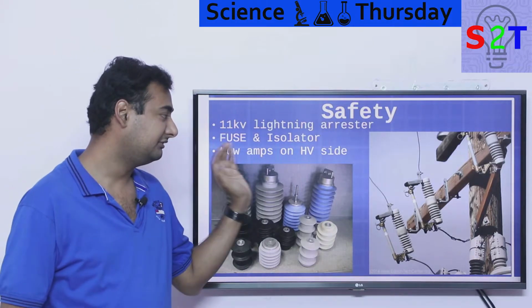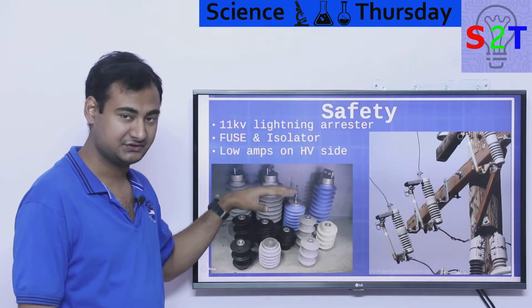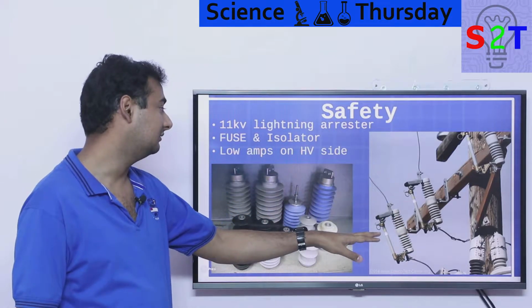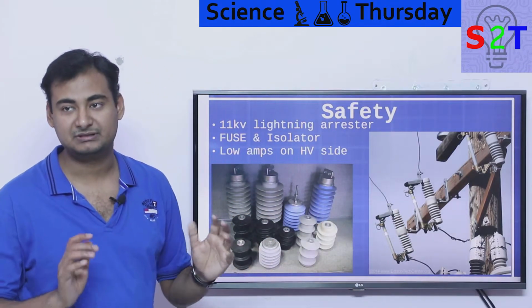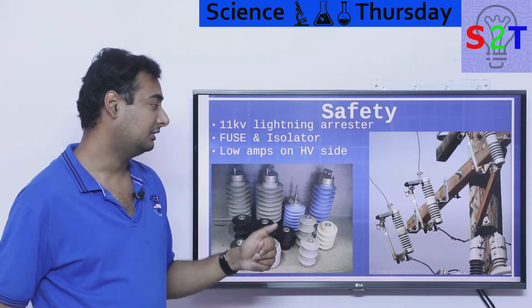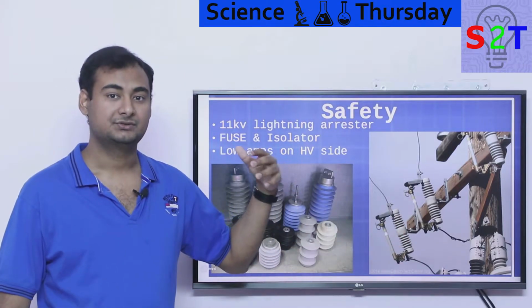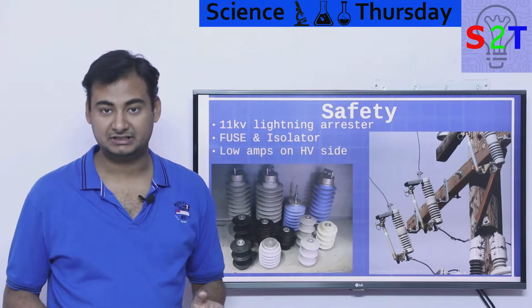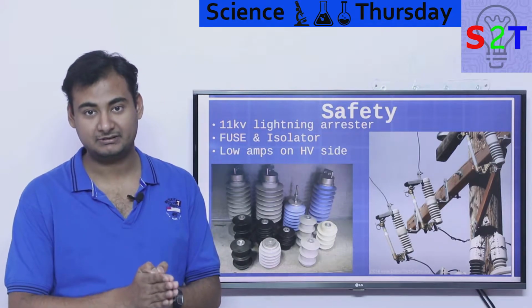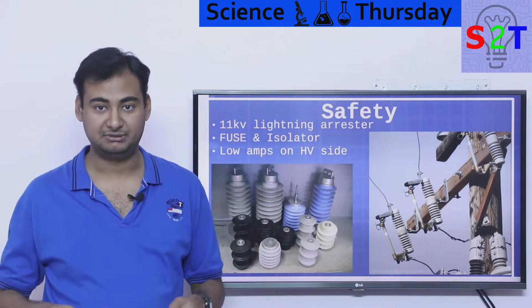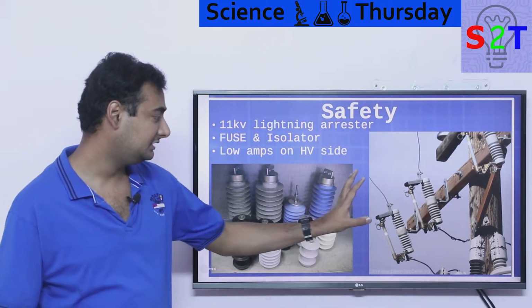On top of that, after this first line of defense, we come to the fuse and isolator. Isolator simply means you are pulling the plug. You have to understand this is a combo unit; in a substation these two would be completely separate, a fuse controlled by a circuit breaker and an isolator completely independent. Here we don't have the money, so we generally rely on this combined unit.